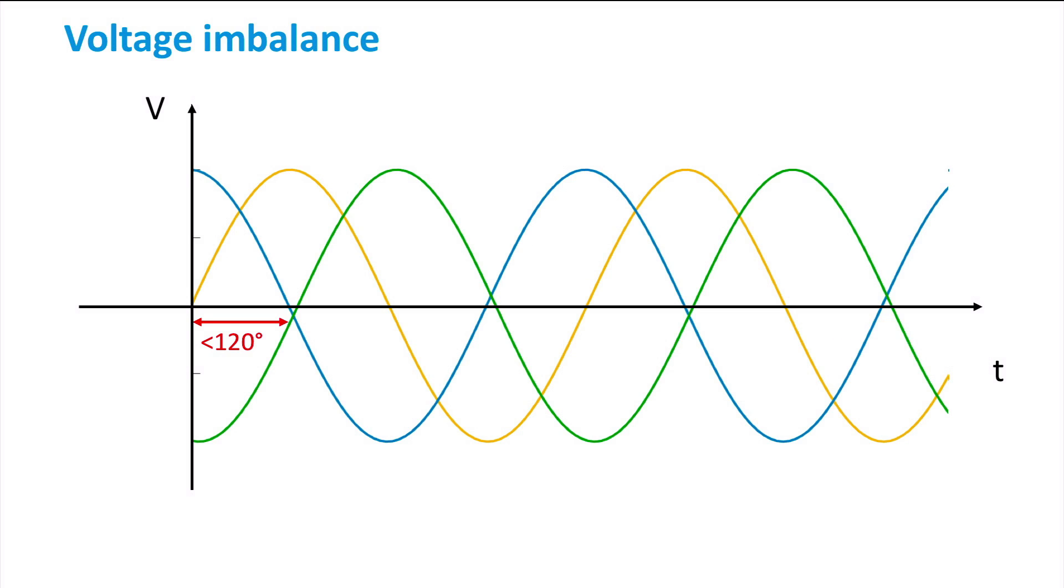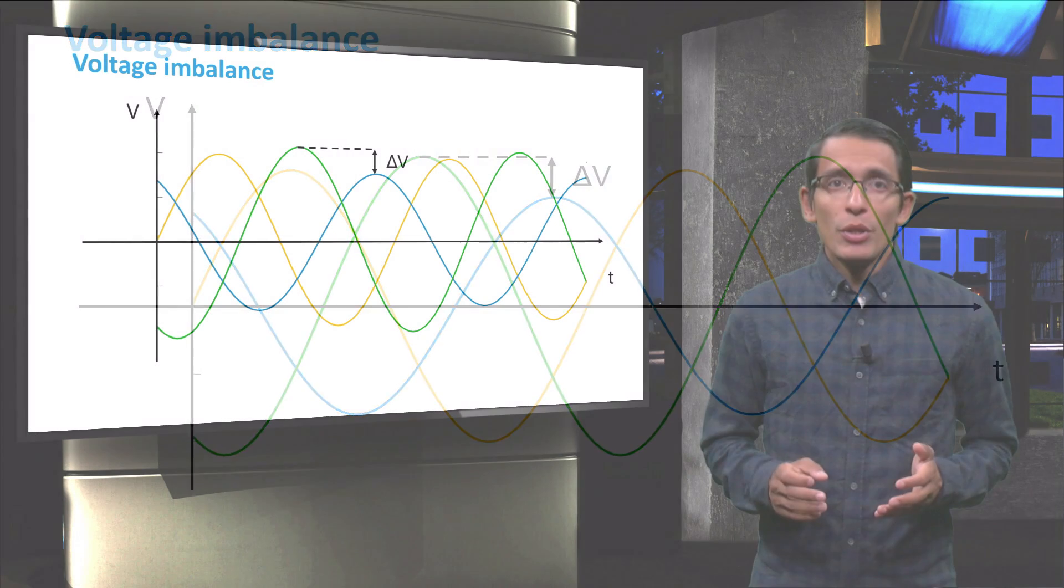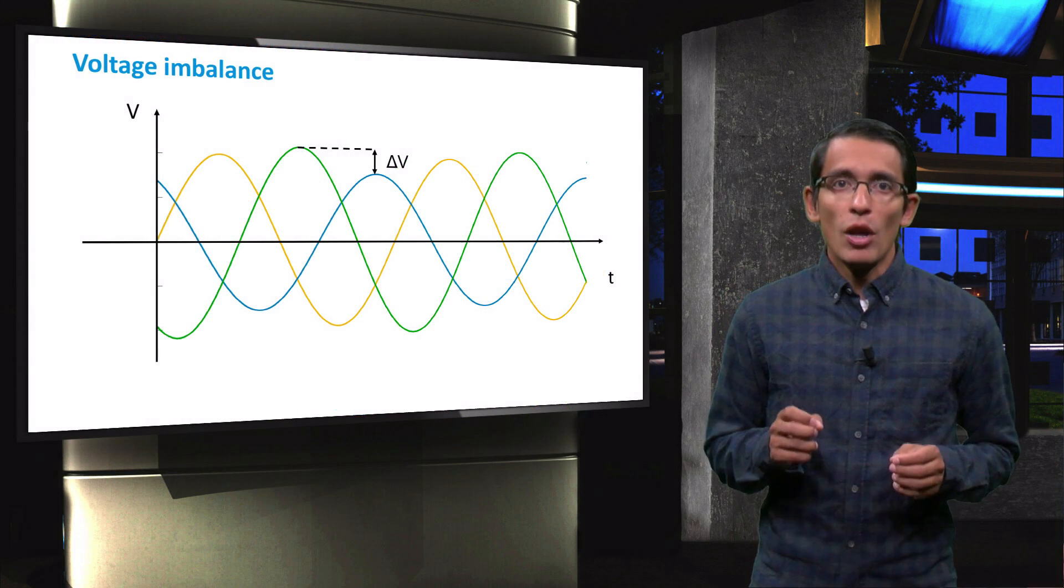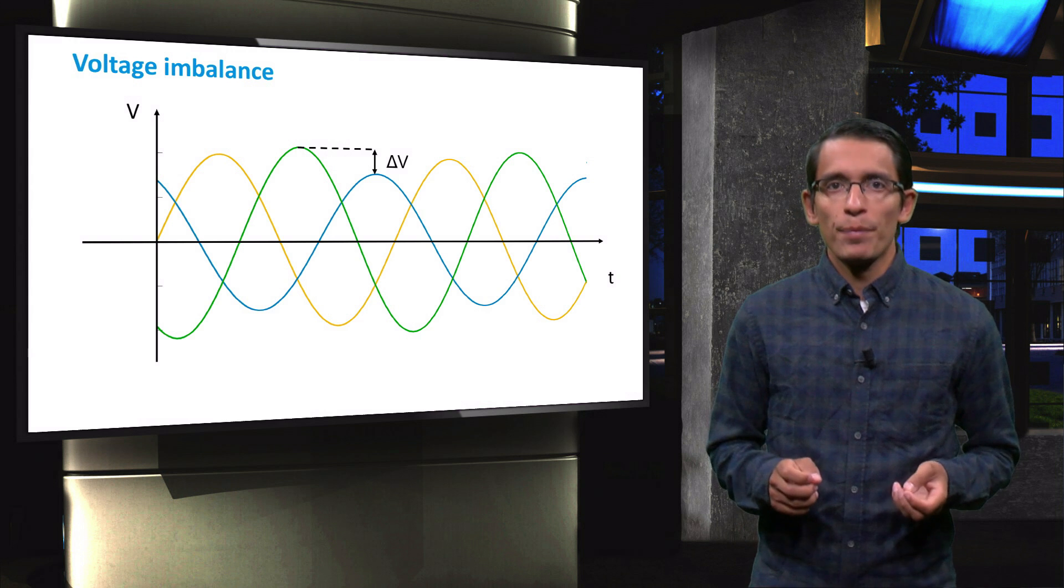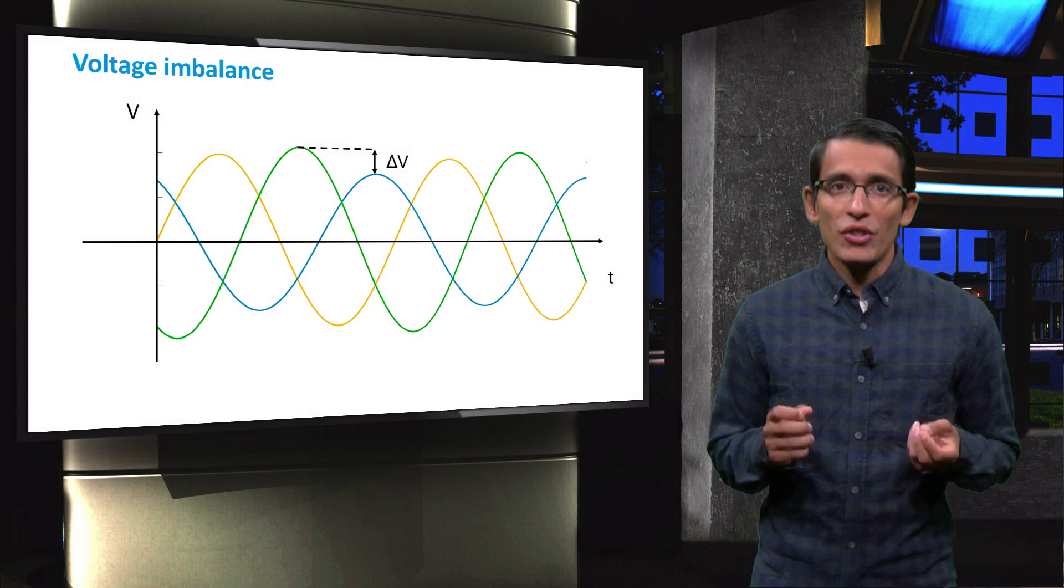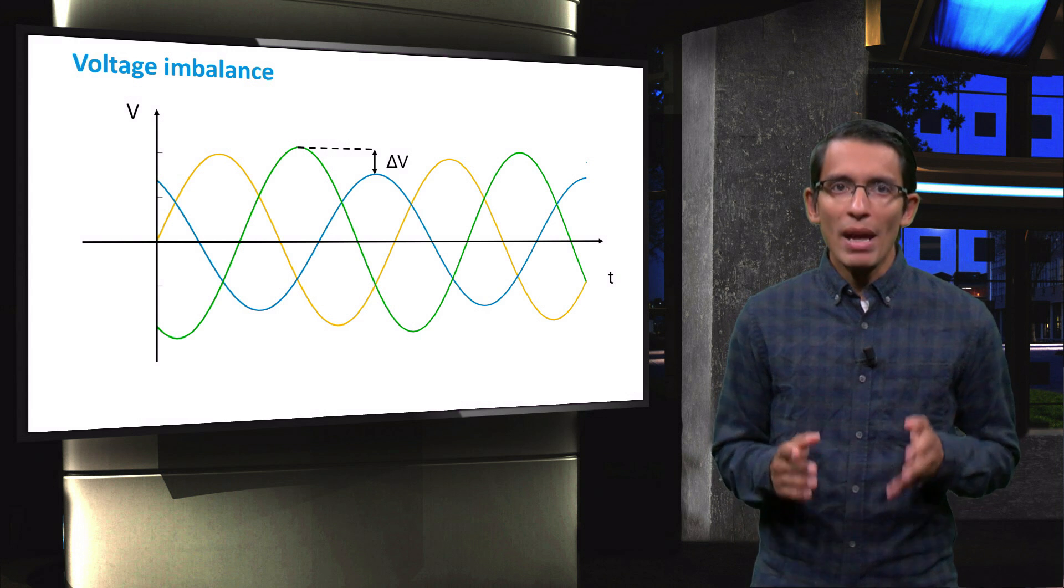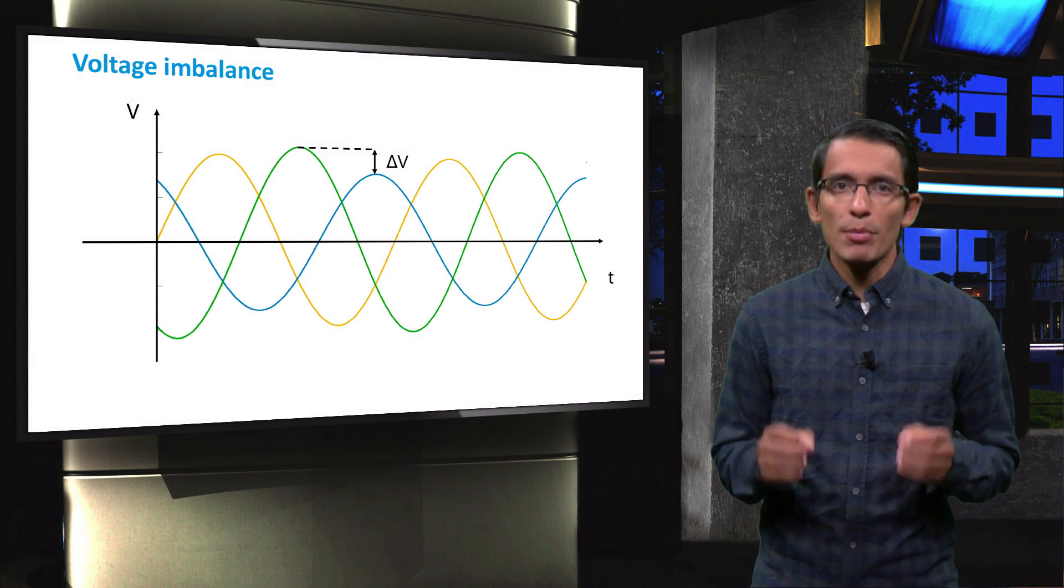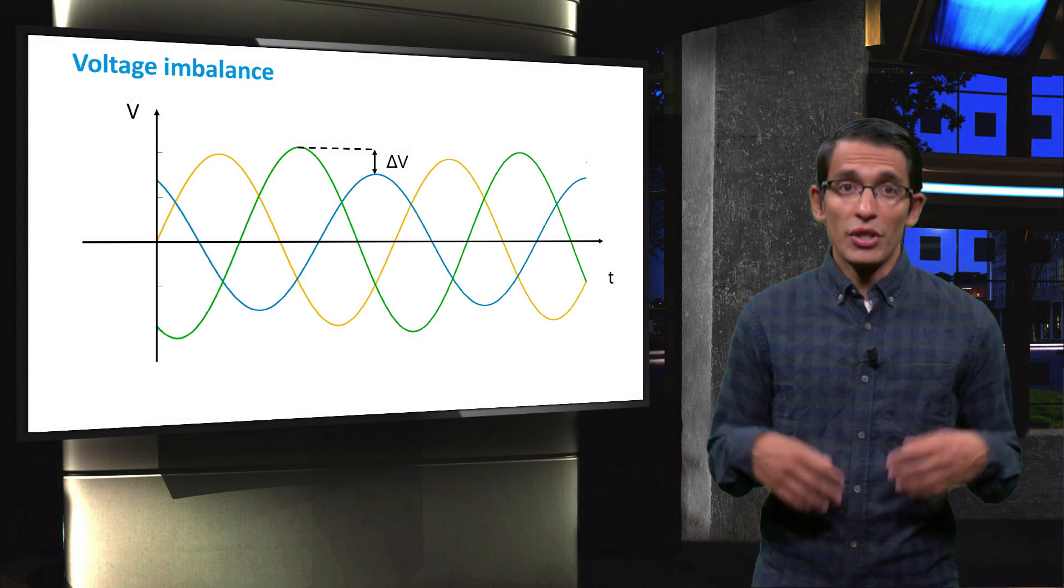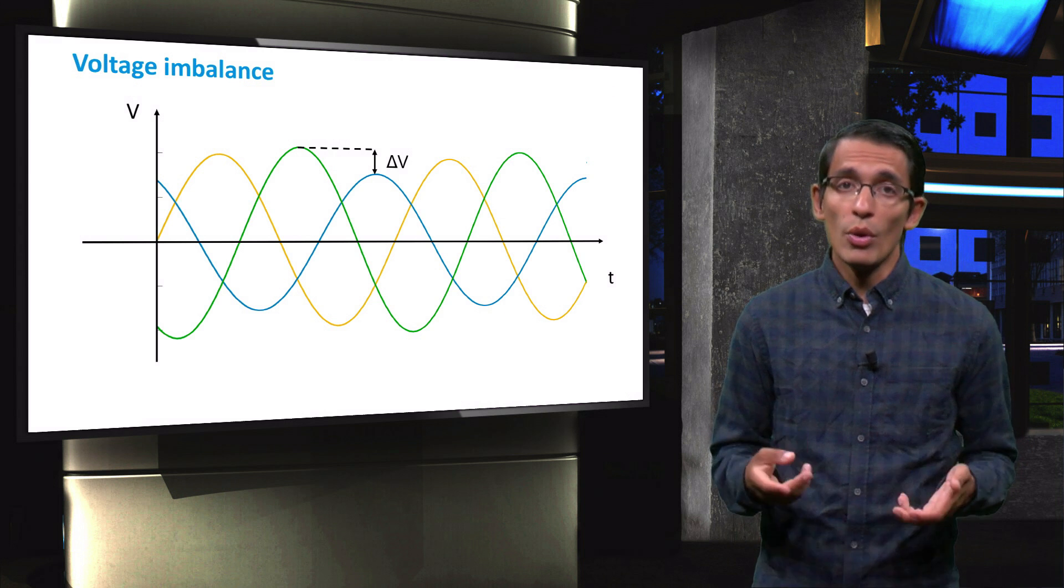Problems will occur if the phase difference changes to a value other than 120 degrees. Also, when the amplitude of the voltage is not the same for all the phases, imbalances can occur. So, if a single-phase generation gets distributed in the three-phase system, this can lead to an imbalance that will have a negative impact on small distributed generators, such as temperature rise of the rotors, noise, and vibration.